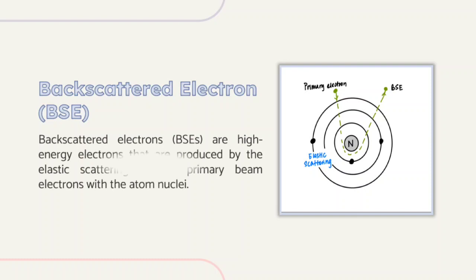Backscattered electrons, BSEs, are high-energy electrons that are produced by the elastic scattering of the primary beam electrons with the atom nuclei. The yield of BSEs — that is, the ratio of the number of emitted BSEs to the amount of primary beam electrons — depends on the atomic number. The higher the atomic number, or the heavier the element, the brighter the contrast.